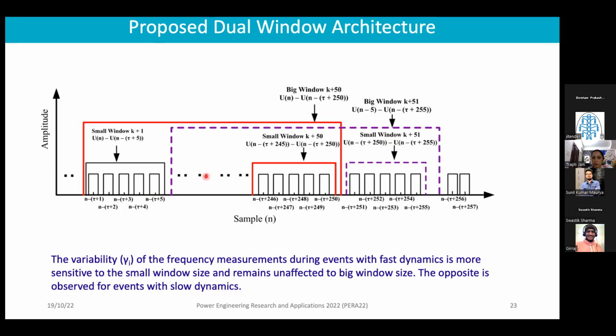Okay. So why have we considered 2 windows? Because we found that the variability of the frequency measurements during events with fast dynamics is more sensitive to the small window size. If we have more samples, then once the signal has settled down to steady state, those steady state samples will push down the variability. It will then indicate that no event has happened, so we can miss the event. But events with fast dynamics were found to be unaffected by big windows. And for events with slow dynamics, because the dynamics are slow, you need to include more samples so that the variability crosses a threshold. So that is how we decided.